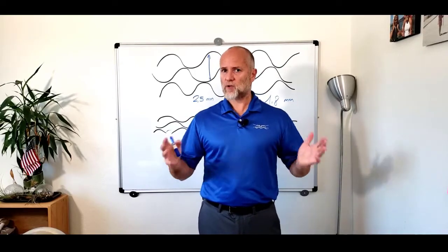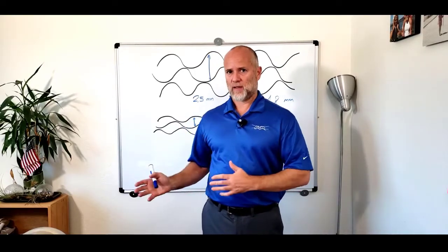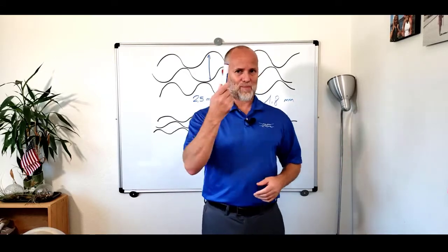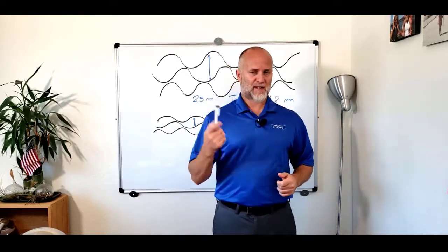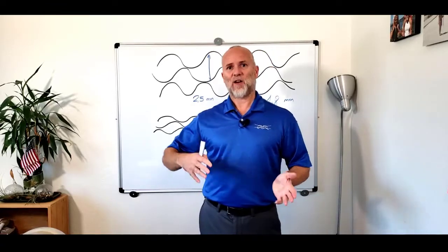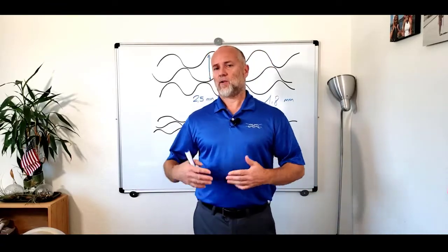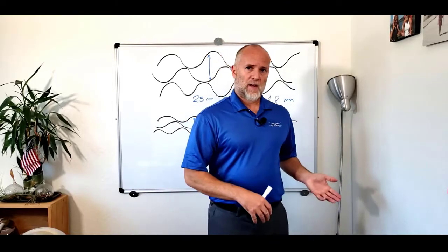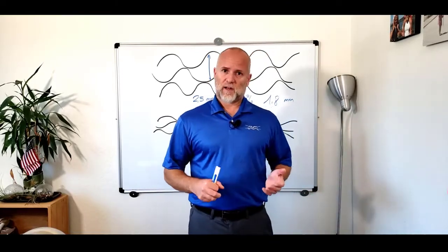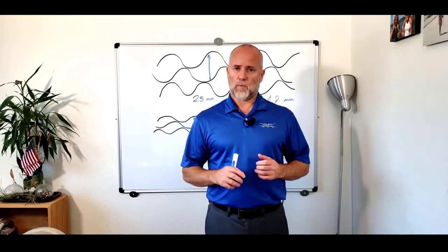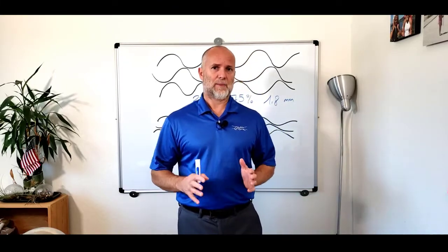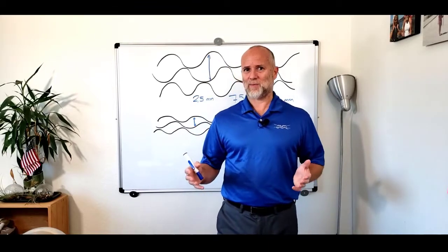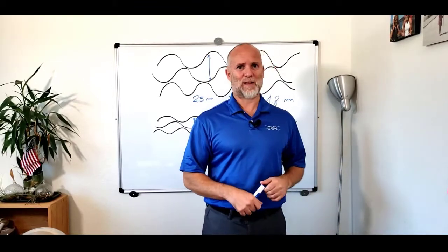When you have a new system, you have all the contaminants, the washers, paper clips, pans, whatever, hats, that you have in the piping, particularly if you have fairly large piping. It's not uncommon, and they end up in your heat exchanger. So definitely pay attention at startup. It's the critical time and the most important thing to pay attention to. You don't want to start up a new system and then have to open the heat exchanger immediately because it's completely fouled.